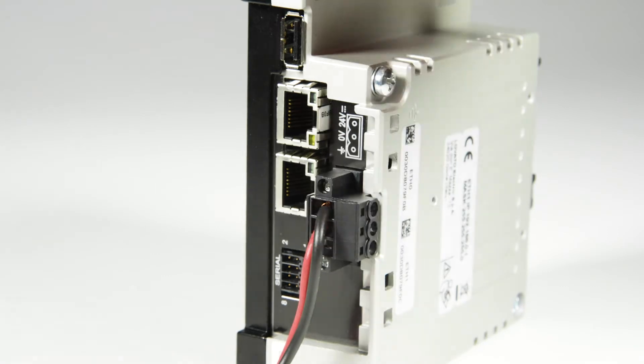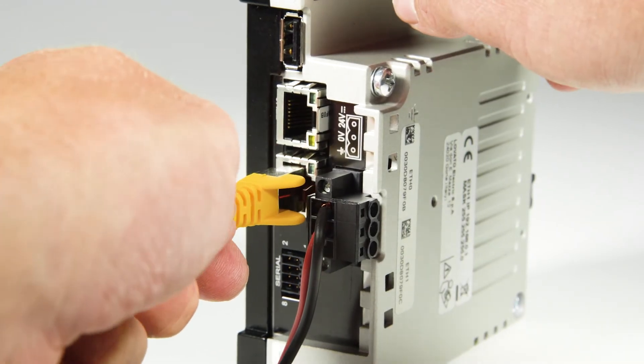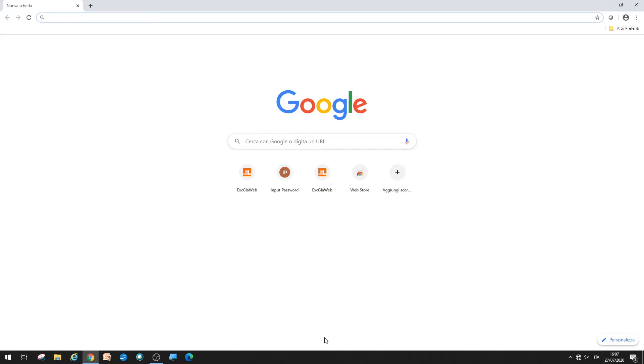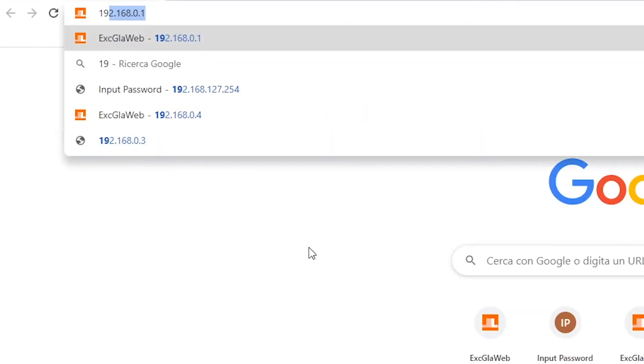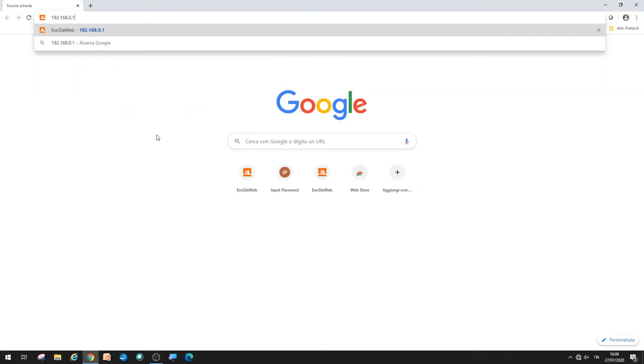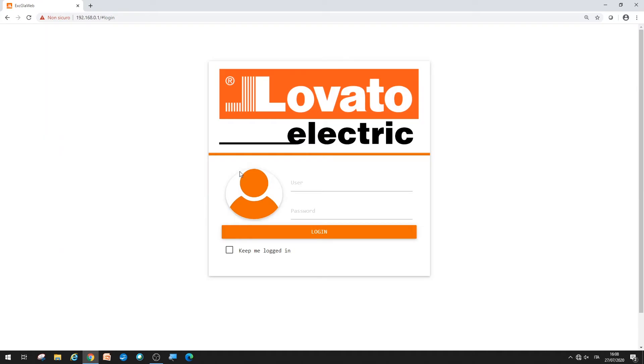First, make sure your PC has an IP address in the 192.168.0.x range. From any browser, enter the address specified on the gateway data logger to configure it: 192.168.0.1. Now you can access the integrated web server. Enter admin as your username and admin also as your password.